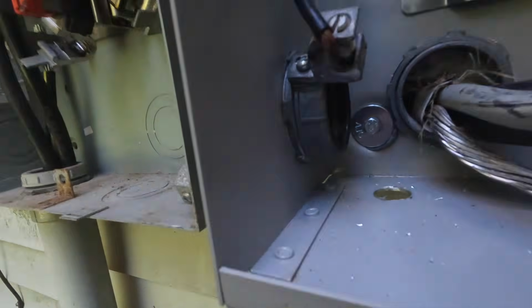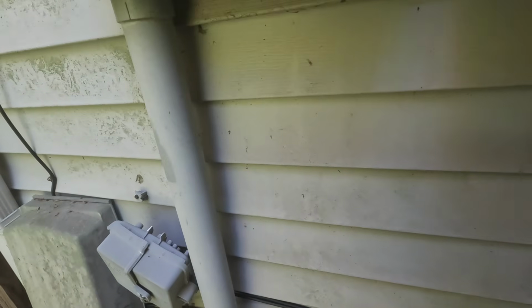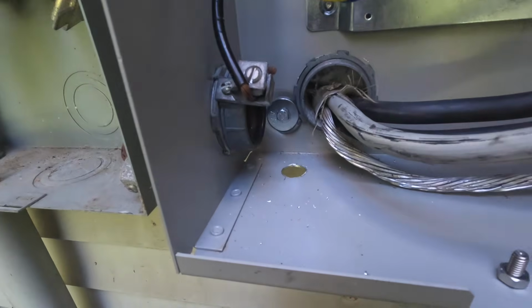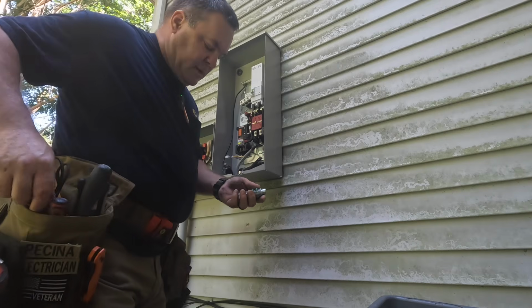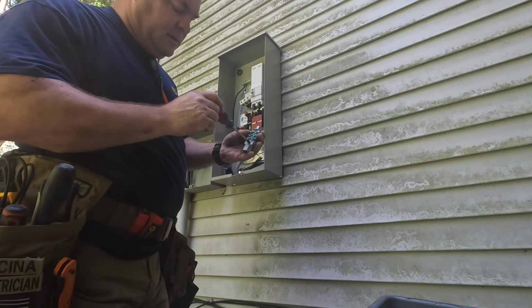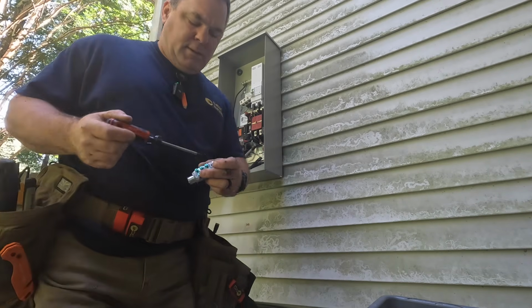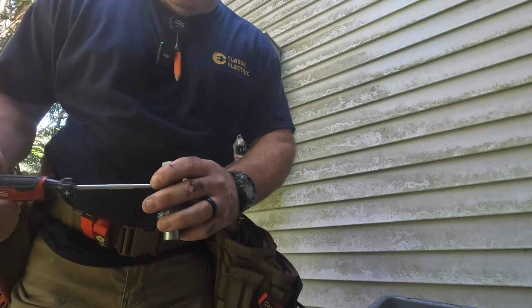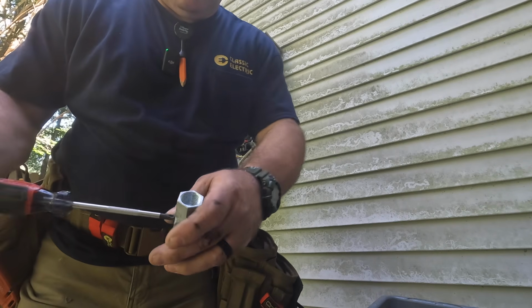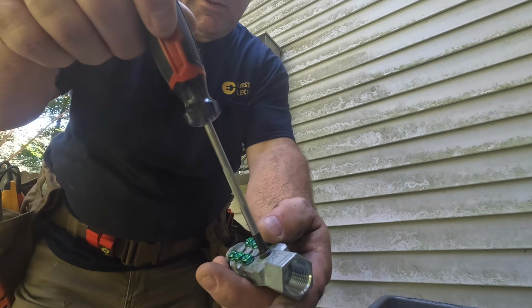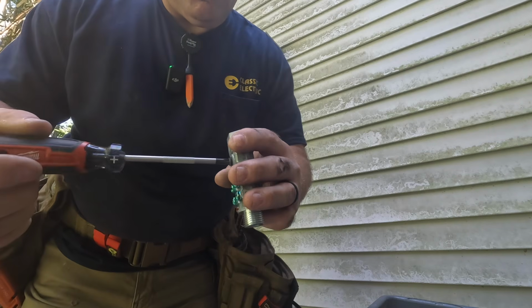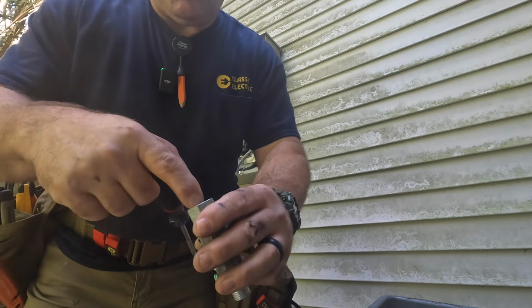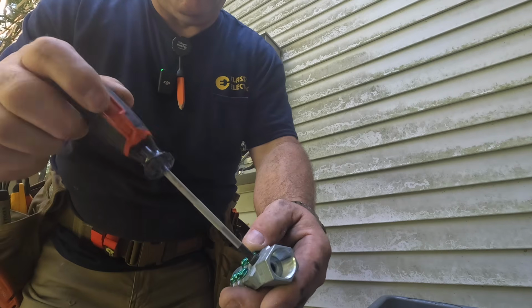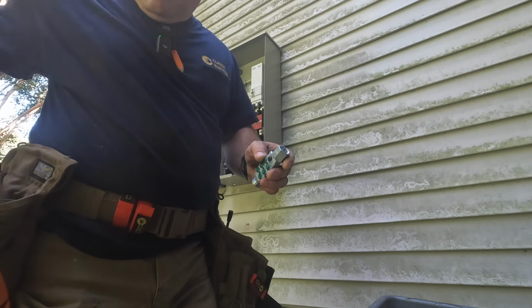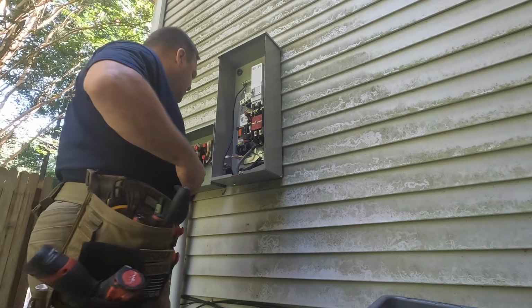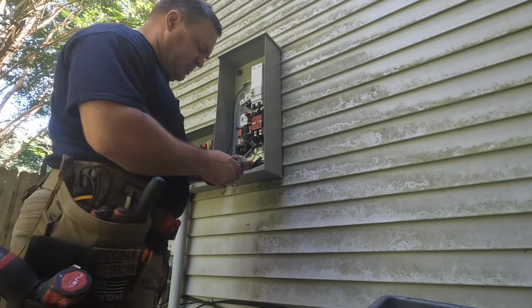You see that just makes a little half inch hole right here, so I can put my bonding bridge in there. What ends up happening with this is there's a little set screw right here that actually makes that physical connection to the bonding bridge right in the middle there. See the set screw? Right in the middle. So when I run that wiring up in there, I'll strip it right at that point so I can make a connection to it. It will be bonded obviously through the enclosure, but the manufacturer has this there, so we're supposed to use it.